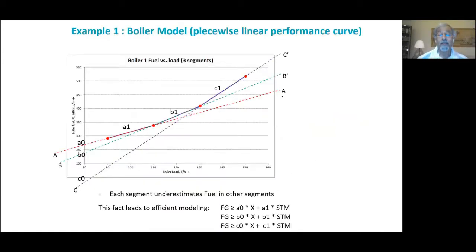Okay, so this still assumed a linear fuel versus steam relationship. The relationship could be more nonlinear for your boiler, in which case you can approximate it by multiple linear segments. Here I'm showing 3 segments. Each one is a straight line. You have the equation for the line, and the model can be modified. The performance equation could be replaced by these 3 inequalities, and this will just follow this curve completely. Again, we don't have time to discuss this, but you can test it for yourself.